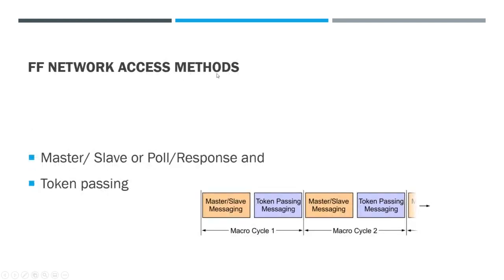Network access method for foundation field bus. Master slave, same as HART, poll response, same as HART. Or we see a new one here called token passing. Call it hot potato, if you like. This is where if you have the potato, or the token, you get to talk. So the master will send out this token. The slave that has it gets to send information, then gives the token back to the master. The master passes it off to the next slave, and so on and so forth.